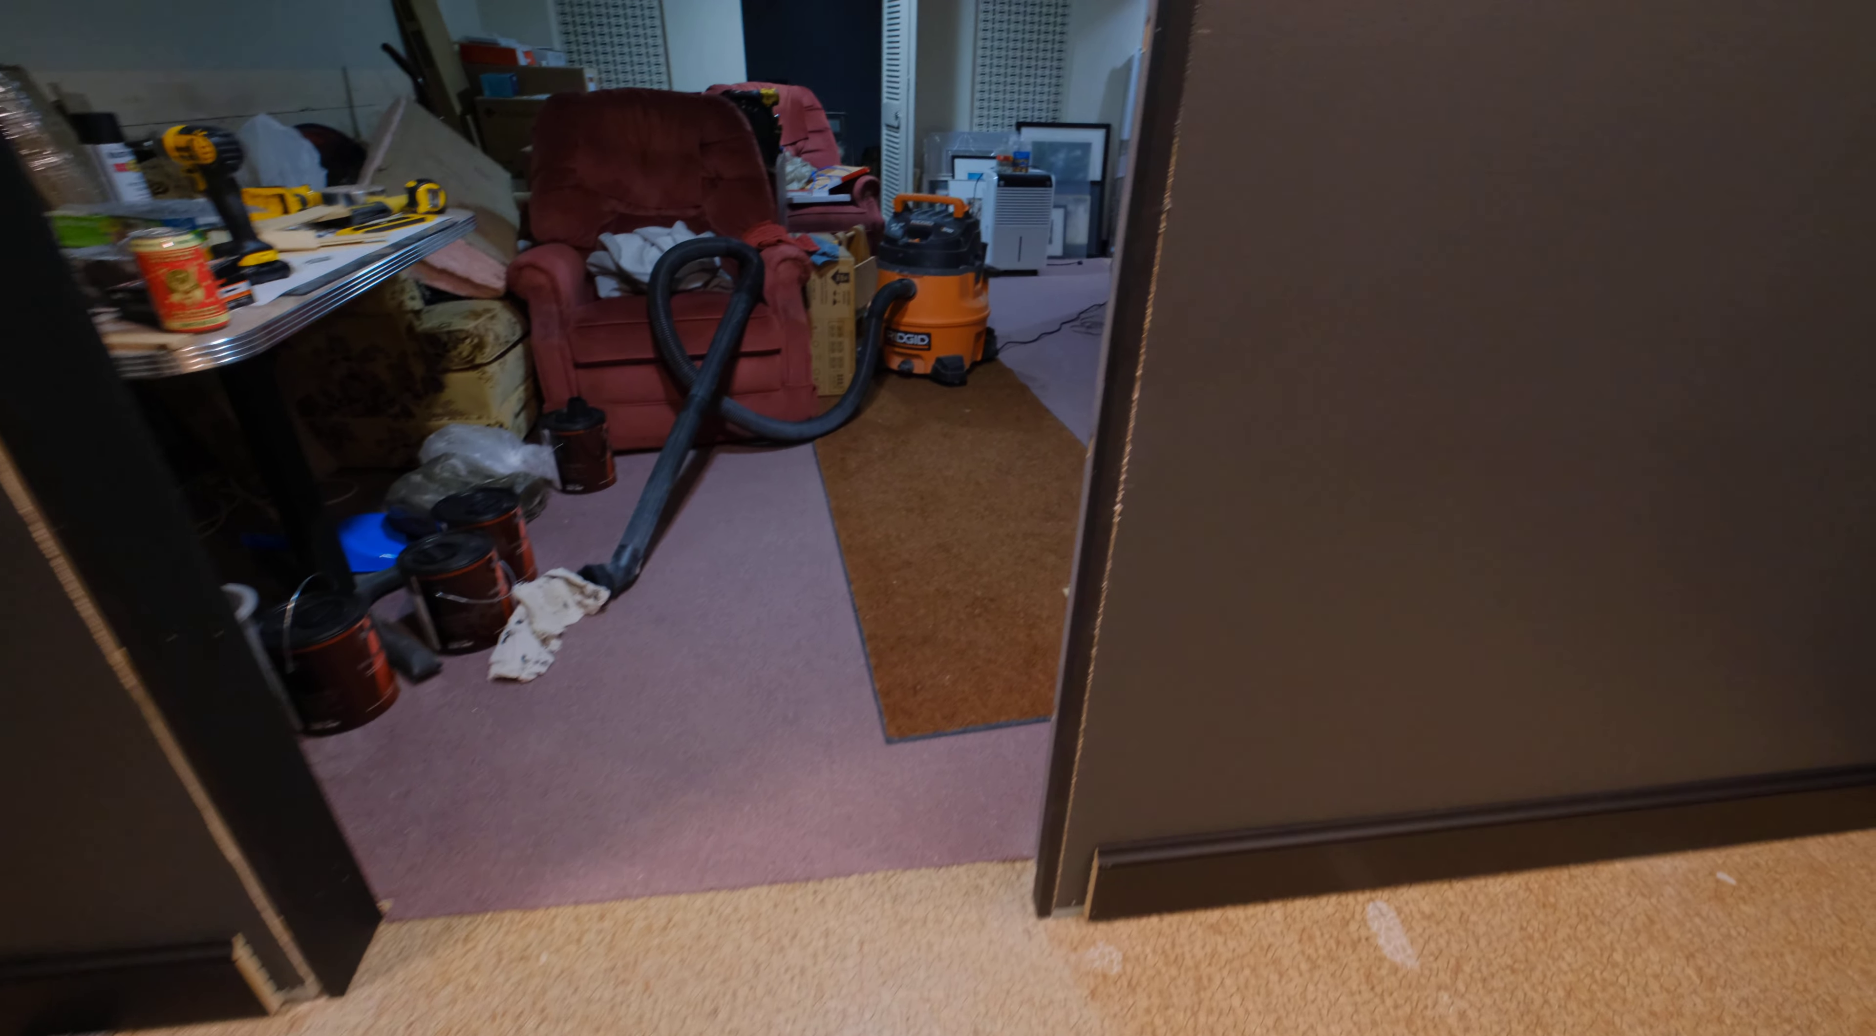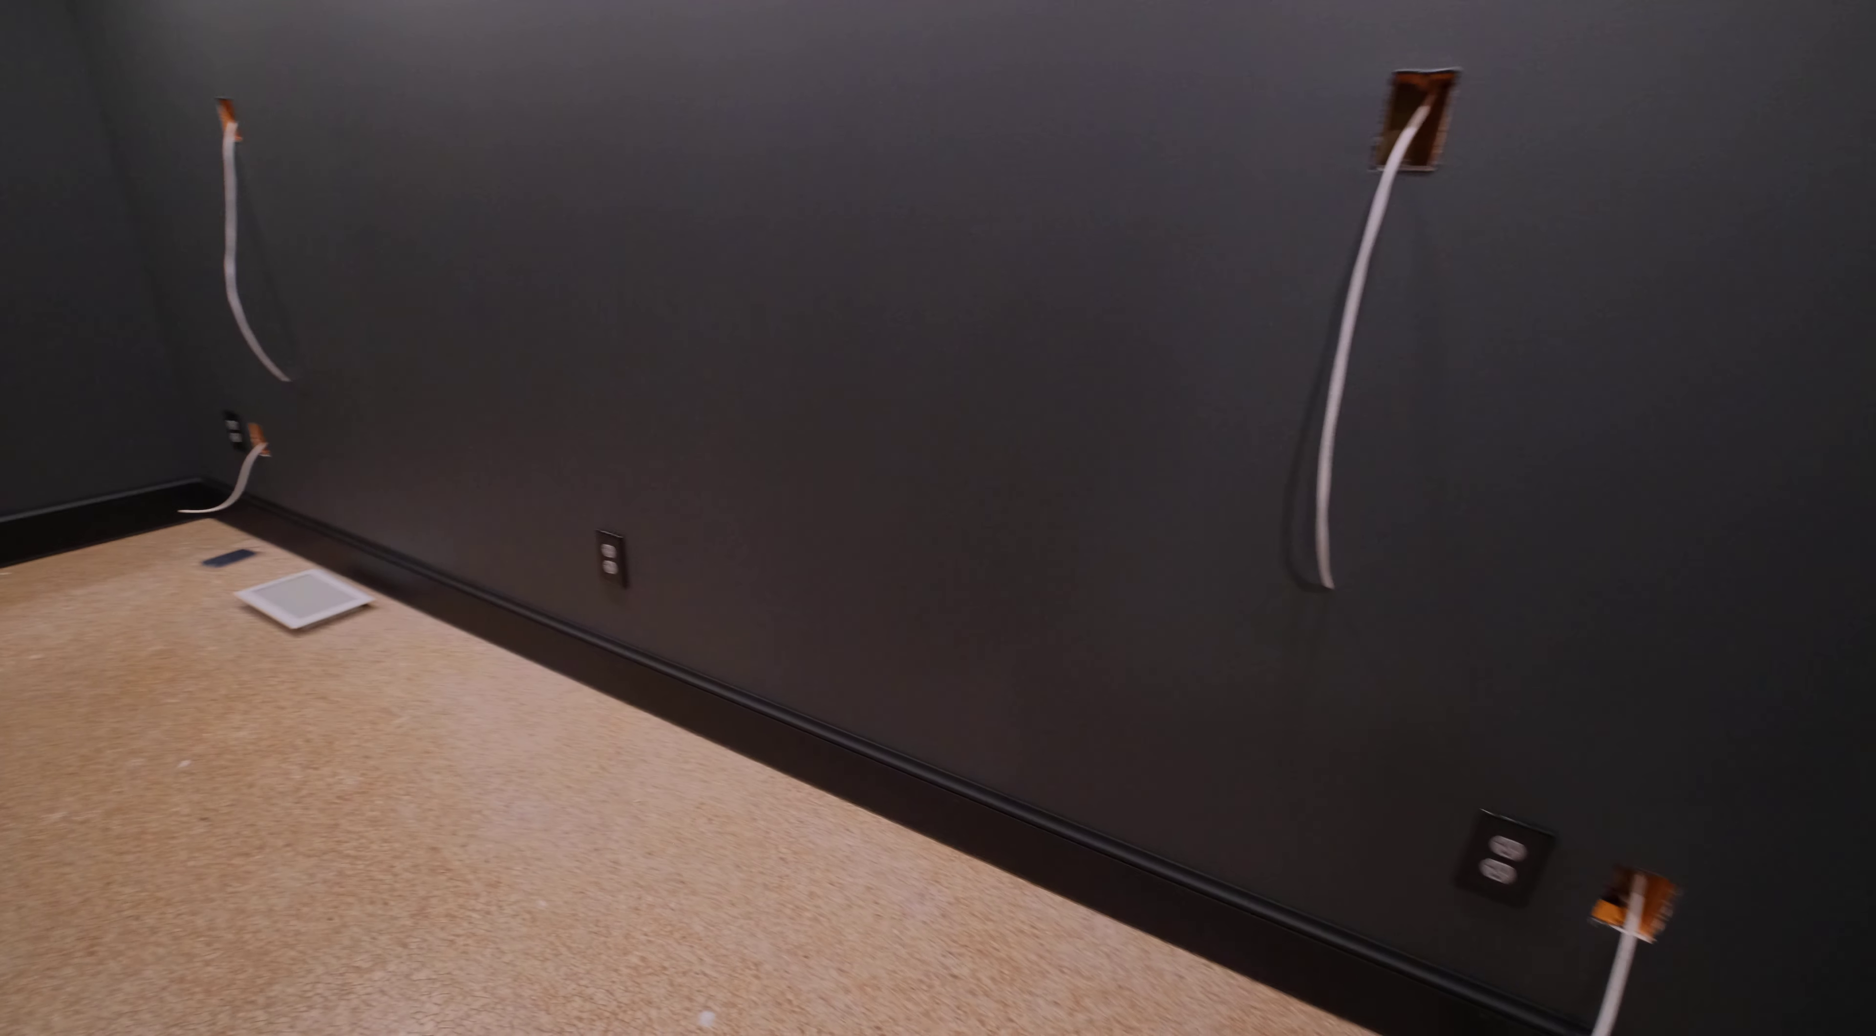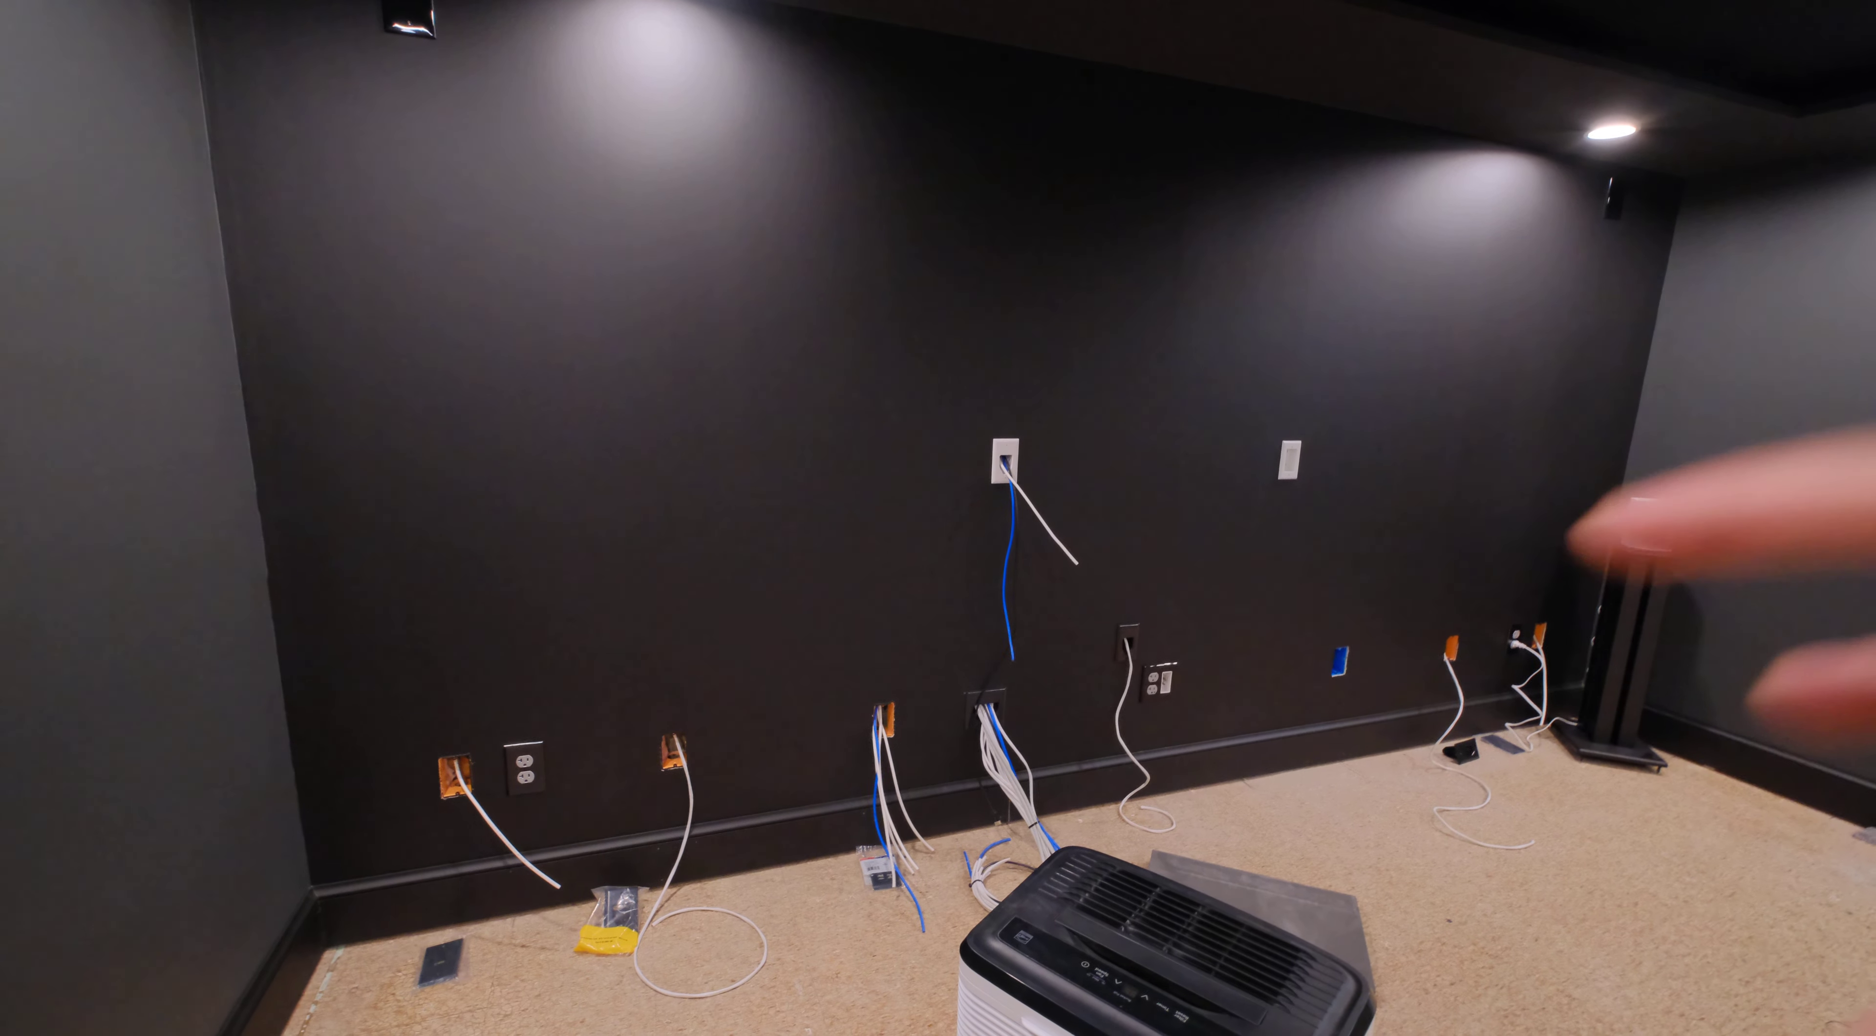Did the terminations for the outlets, three in the back which those ones are actually on the lighting circuit. But that's really just for power recline for the chairs and vacuuming or whatever. But I didn't want it on the circuit with the equipment or the lights for that matter. The equipment is on its own 20 amp circuit with like I said before a 10 gauge wire.